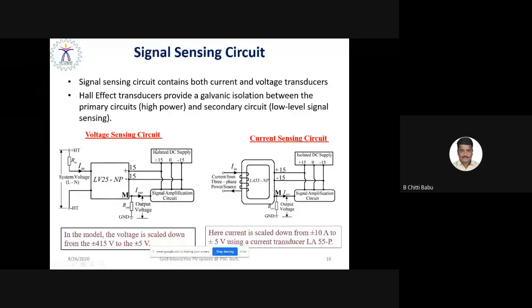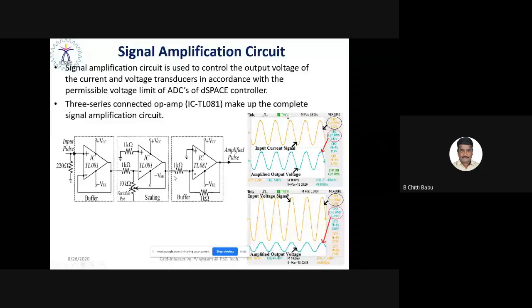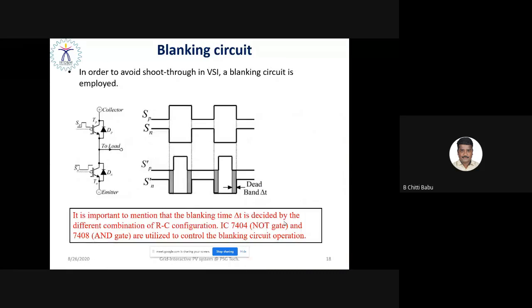Okay, so this is the signal sensing, as we sense the 3-phase AC voltage. For the voltage sensor, we used the LV25NP Hall effect sensor to scale down the voltage from 415 volt to plus or minus 5 volt. Moreover, the current sensor scales down the supply current from plus or minus 10 ampere to 5 volt. The available 5 volt from the current sensor and from the voltage sensor is given to an amplification circuitry, since the amplitude of the sensor output is not enough to drive the interfacing with the dSPACE. So we use a 3-phase cascaded amplifier with the TL081. You can see the input current signal and the amplified output voltage level, so that we are able to amplify the signal available at the sensor, which is then given to the dSPACE interfacing card.